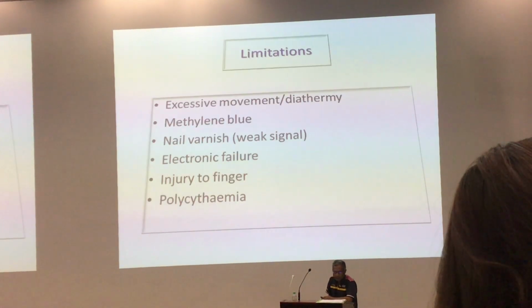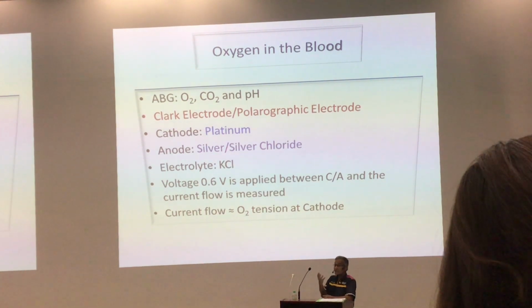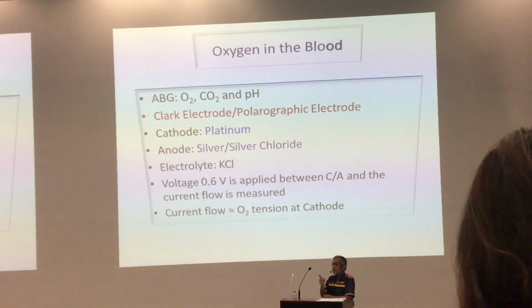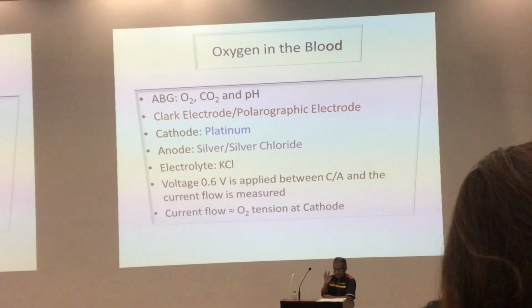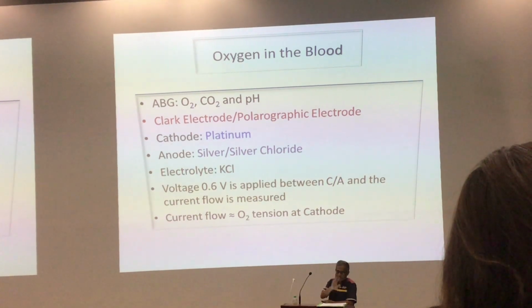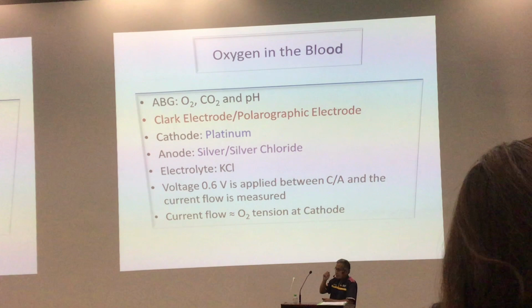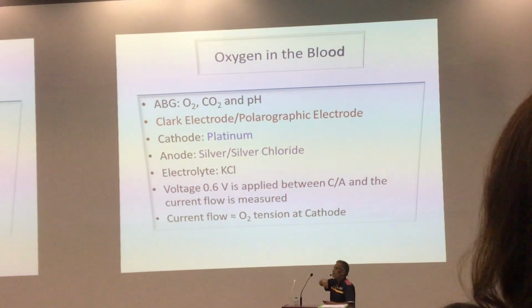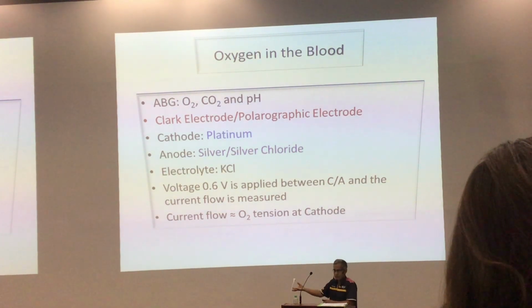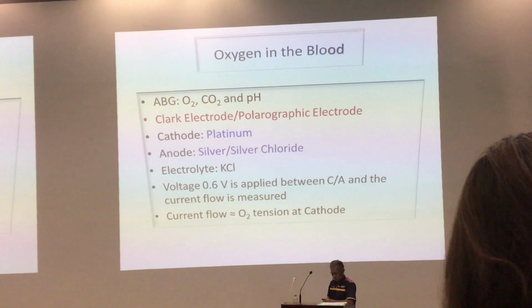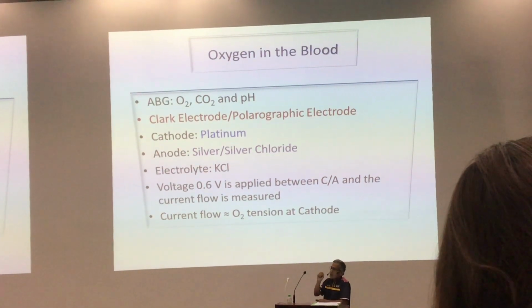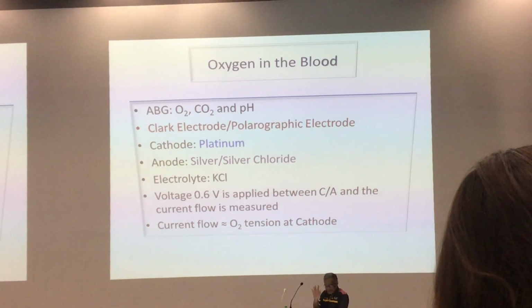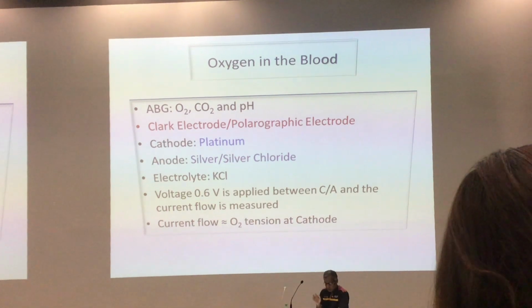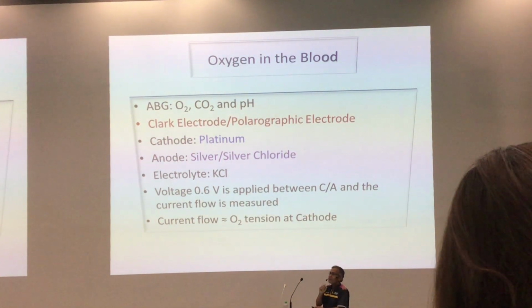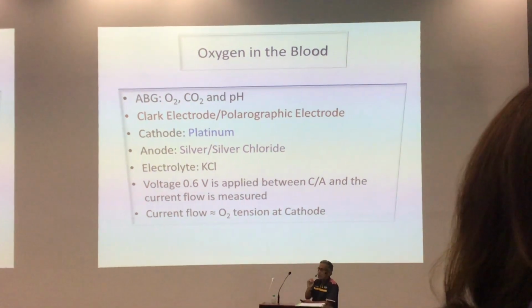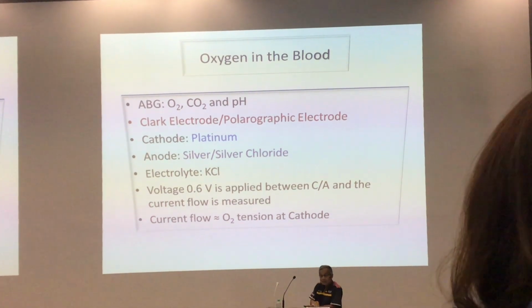So now, same as measuring oxygen in the blood. Just now with SpO2, you measure oxygen saturation in the capillary blood. Now if you want to measure oxygen in the blood, you use the ABG machine, right? So basically, you get arterial blood from your arterial line and send it to the ABG machine. The ABG will interpret it, you get the PaO2, how much, right? From PaO2, you can calculate SpO2. So basically, the device they use is the oxygen electrode. You don't have to know the detail. The oxygen electrode is also called the Clark electrode or polarographic electrode. That's it. So if in the MCQ they ask you the device, machine, or equipment used to measure oxygen in the blood, this is the equipment.